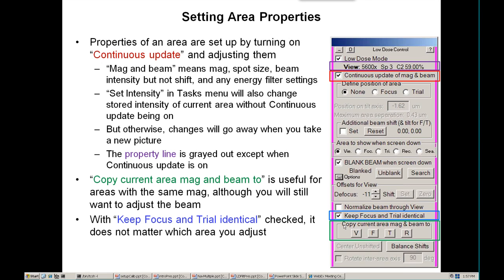A handy set of buttons when setting things up: if you've just set a new magnification for your record, you can copy it over to the trial and focus areas to have those at the same mag, though you'll still want to go to them and adjust the beam separately. There's also an option that keeps focus and trial identical. Almost everyone probably does it this way, but there are some special cases where you might want them separate. When this is checked, it doesn't matter which area you're in when you adjust their properties — they're kept tied together and always the same.